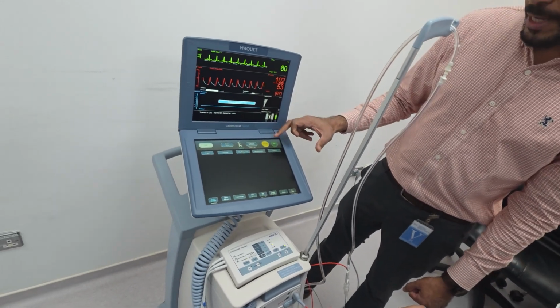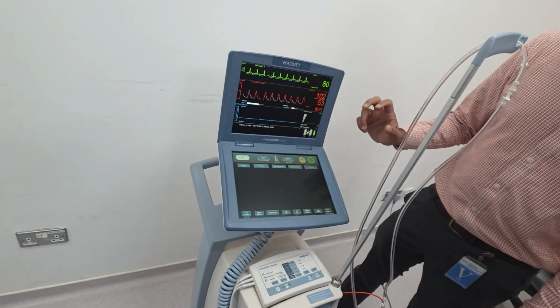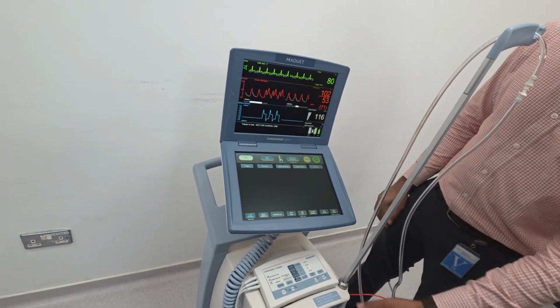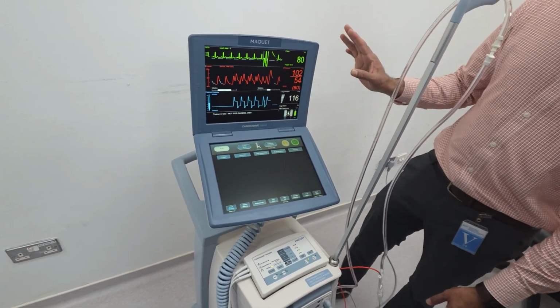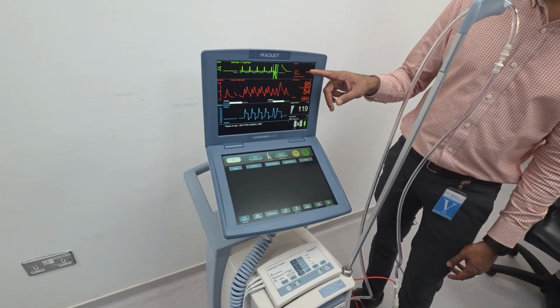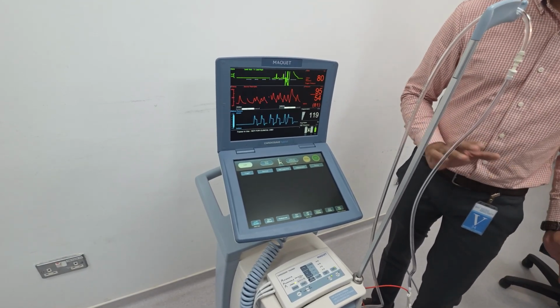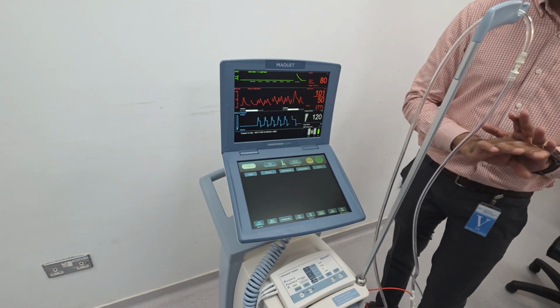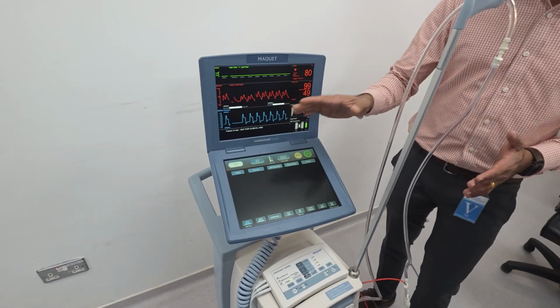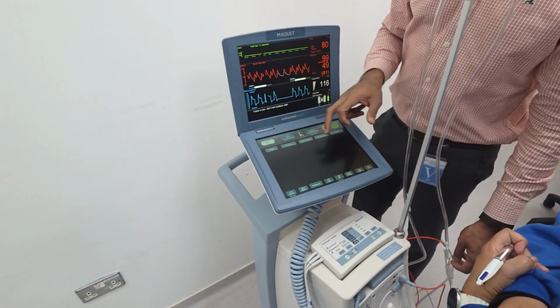Okay. Now it's saying like CS300. Once you start it, we are in auto mode, right? If something happens to the ECG, there is no ECG. You can see the color is changed. Now it's working with the automatic, it will work because you are in auto mode. If it is semi-auto, it won't work. It will stop working. So make sure that you are always using auto. Okay, now we are in auto mode.